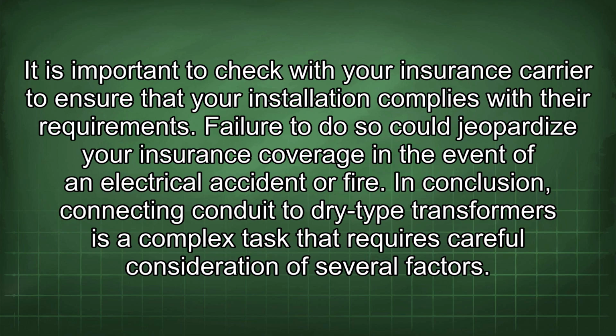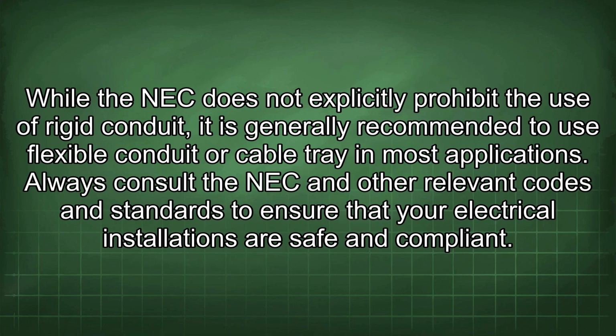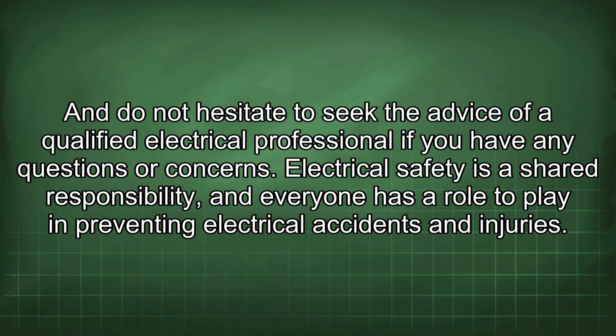In conclusion, connecting conduit to dry-type transformers is a complex task that requires careful consideration of several factors. While the NEC does not explicitly prohibit the use of rigid conduit, it is generally recommended to use flexible conduit or cable tray in most applications. Always consult the NEC and other relevant codes and standards to ensure that your electrical installations are safe and compliant. And do not hesitate to seek the advice of a qualified electrical professional if you have any questions or concerns.